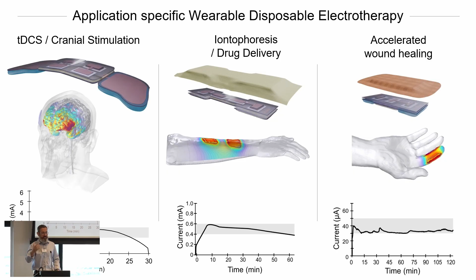Once we design these things and build these things, the main thing we need to validate, like the key functional element, is that when we put it on the body, it gives you a single dose at the prescribed level, right? So if it's the Band-Aid version, it needs to provide somewhere around 40 microamps for 2 hours. If it is the brain stimulation version, we needed to first ramp up. It can't go up instantly in this case, right? We needed to ramp up, hit a target level, and then self-deplete after a certain amount of time, right? And this is across multiple people, who present very different loads.